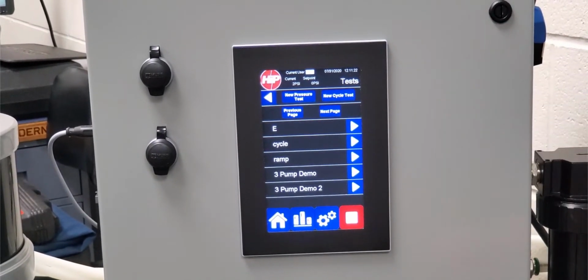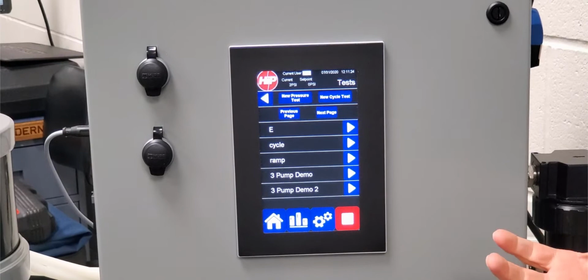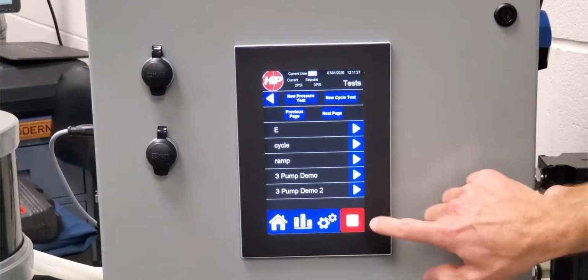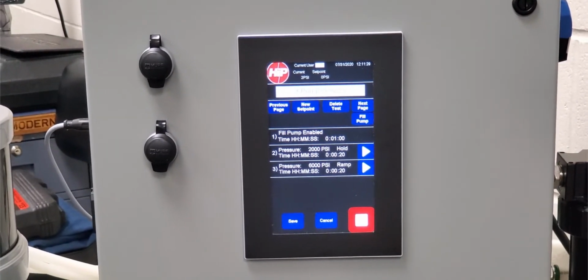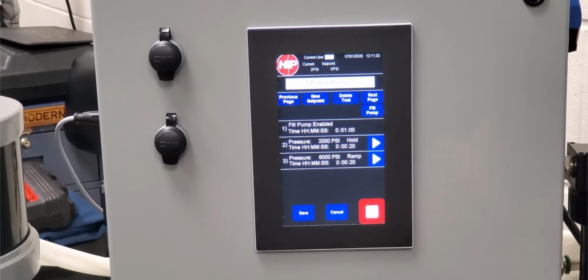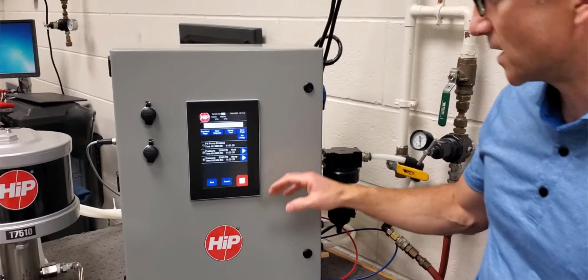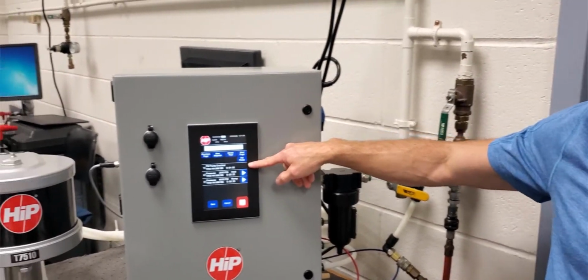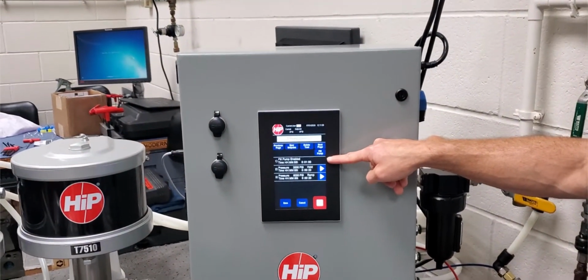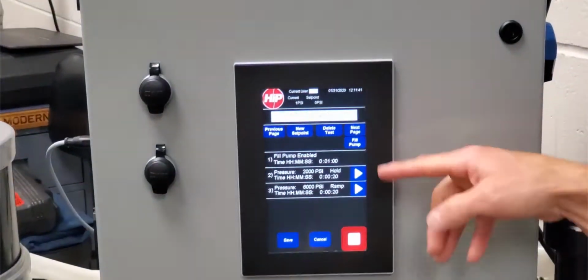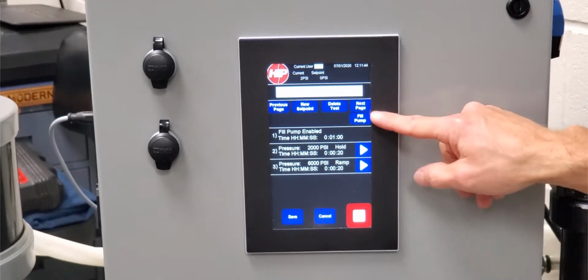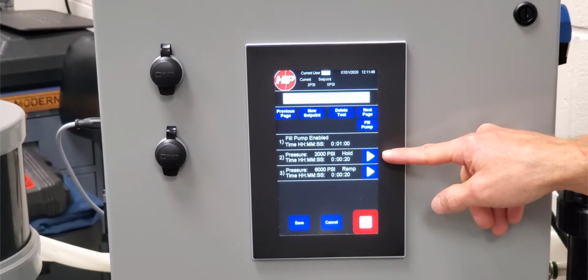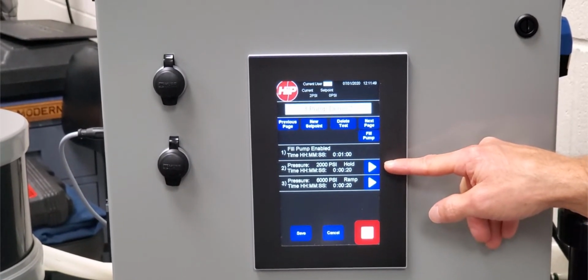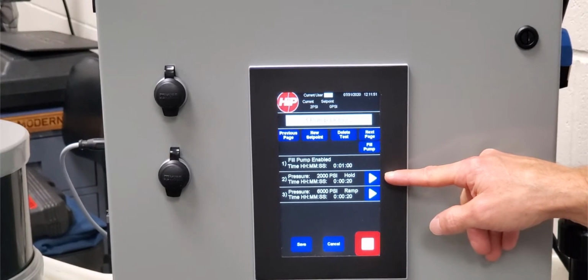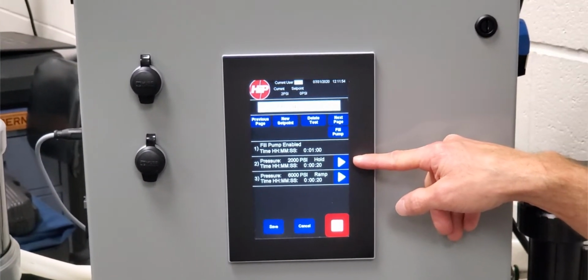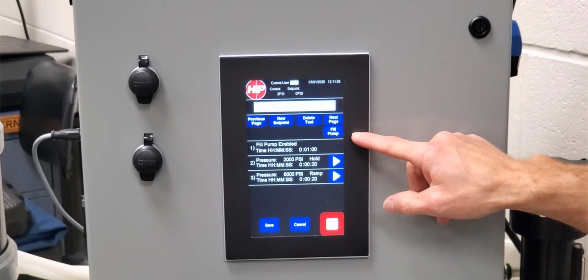From a pressure testing perspective, this is where you really enter in the key features of the controller. So this allows us to do ramping or cycling tests at given pressures for whatever your needs are. So in this example, we're going to turn on our fill pump, and it's going to run the fill pump for 1 minute to bleed the air out of the system. Then the next test will run as quickly as we can up to 2,000 psi, and it's going to hold at that pressure for 20 seconds. That will be run with the first pump. That's our speed pump to fill.